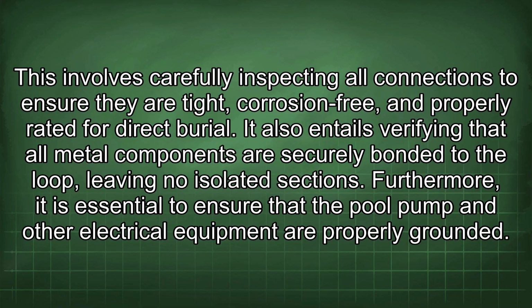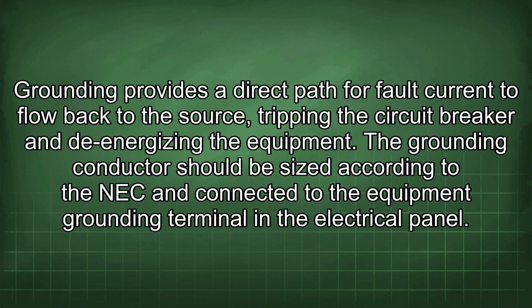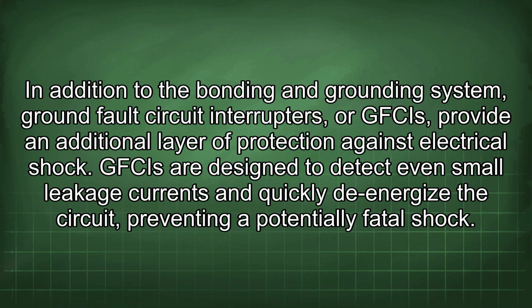Furthermore, it is essential to ensure that the pool pump and other electrical equipment are properly grounded. Grounding provides a direct path for fault current to flow back to the source, tripping the circuit breaker and de-energizing the equipment. The grounding conductor should be sized according to the NEC and connected to the equipment grounding terminal in the electrical panel. In addition to the bonding and grounding system, ground fault circuit interrupters, or GFCIs, provide an additional layer of protection against electrical shock.